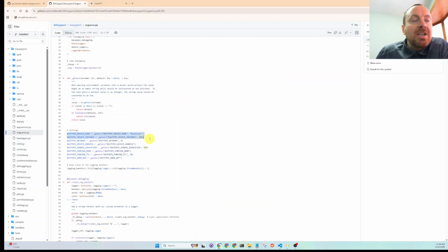That's because even though we're just reading data, BACnet stacks are always an inbound protocol, I think is the way I'm describing this correctly, where the operating system only lets one application at a time listen to port 47808, which is required to even read data.